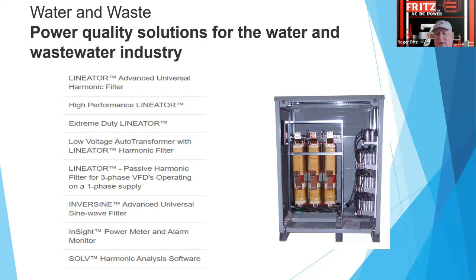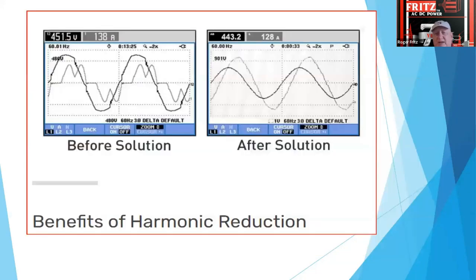This happens to be one type of an LC. They put inductors and capacitors, in parallel and series, into the circuit to clean up. This happened to be in the wastewater industry. This is okay if it's actually more of a constant load capability. But again, the Fluke meter is telling us what that PWM is looking at. It's each individual motor, and it's showing the resultant voltages, and it gives us those values. This is before and after the harmonic resultant that was in there.